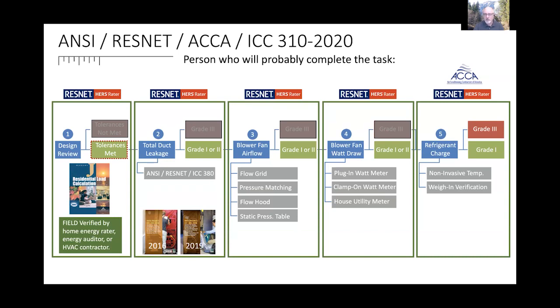Then we get to one of the major problems. Earlier I talked about studies showing it's all about airflow, including duct leakage, but in general the blower motors weren't doing the proper airflow. That's also related to refrigerant charge - they're not totally separate. If you have a problem with one, you probably have a problem with the other. If I've got restrictive airflow inside, I probably have refrigerant charge issues showing up outside. That doesn't mean you just change the refrigerant charge - you need a system-wide approach to find the actual problem.